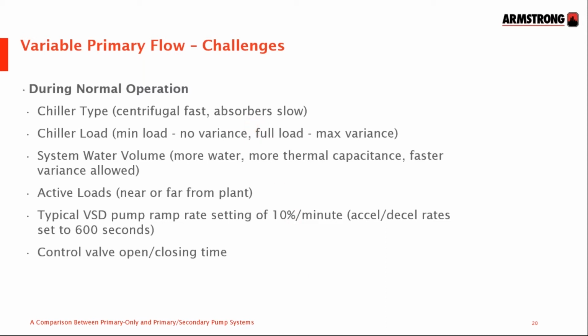The key thing is the rate of change of load at loading. Chillers can accept a faster rate of change when they're fully loaded than when at low load, where they can accept almost no change whatsoever. The other key determinant, which is not really in the hands of the designer, is the amount of water in the system. The more water there is, the more thermal capacitance, the more it will dilute the effect of a change of load, thus allowing a fast change of load. Similarly, if the load is far away from the plant, by the time it gets back to the chillers, the change will have been slowed down.